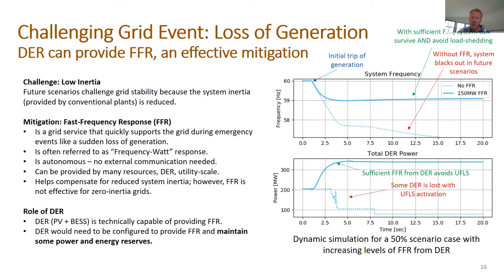You can see the power response from the DER in the bottom trace ramps up very quickly over the course of several seconds and actually avoids under frequency load shedding in this particular case and in many cases, so that not only are you able to avoid a system blackout, but you're able to avoid the loss of a good bit of load that's usually accompanied with such a severe disturbance. In terms of the DER, this is often discussed as frequency-watt response, one of the smart inverter functions.